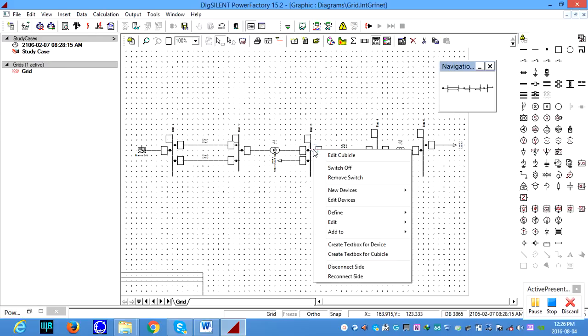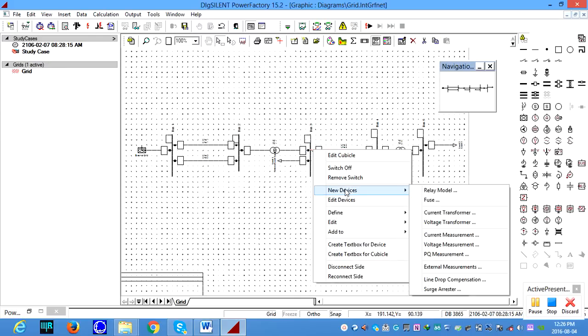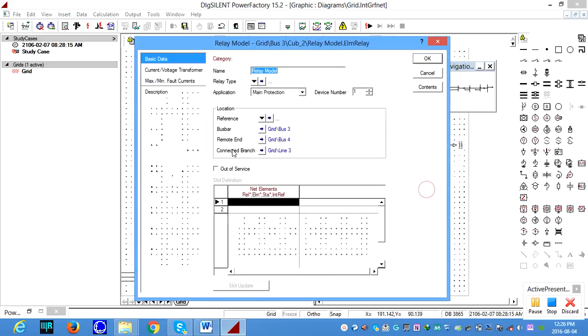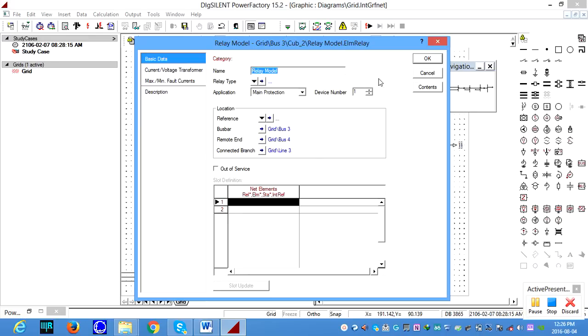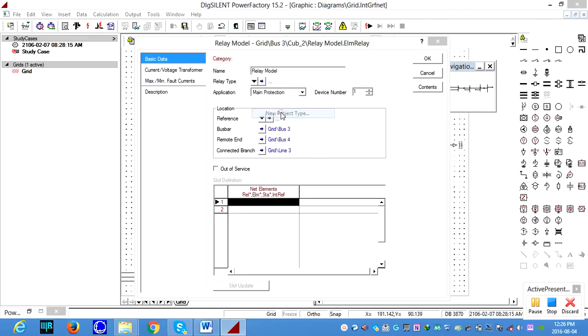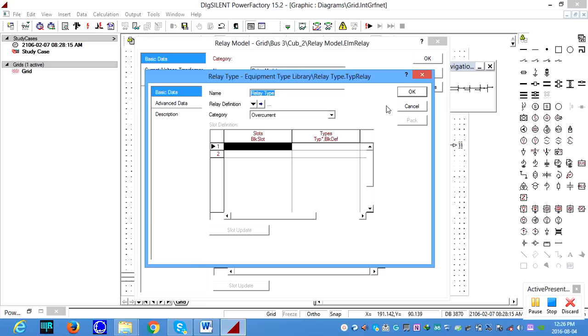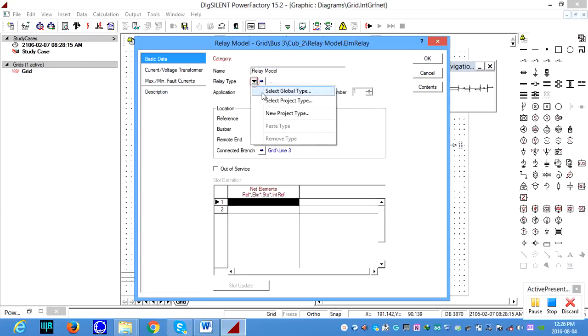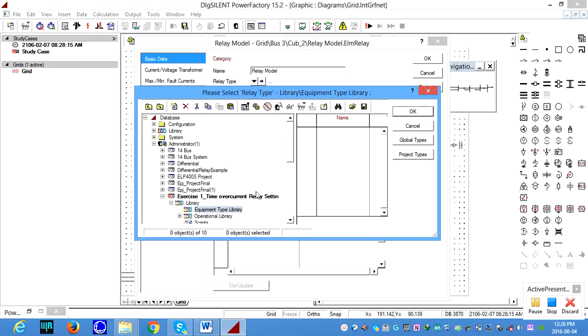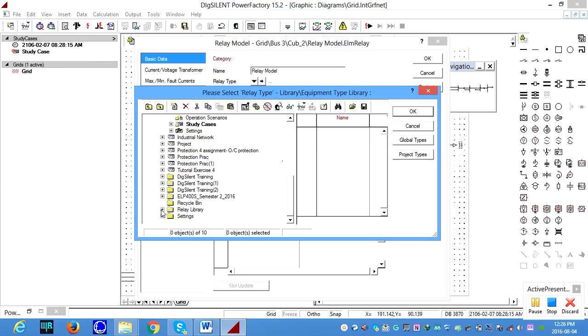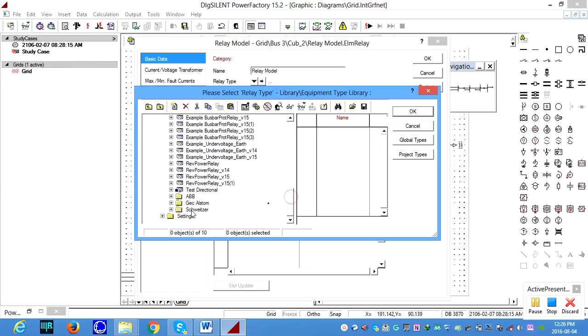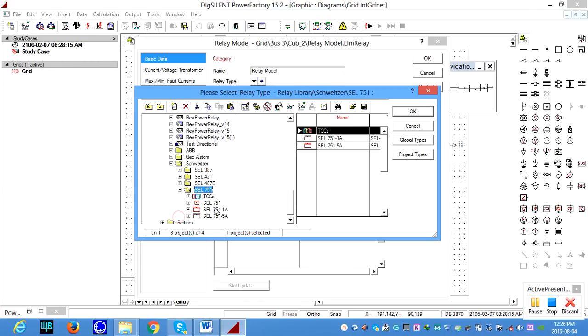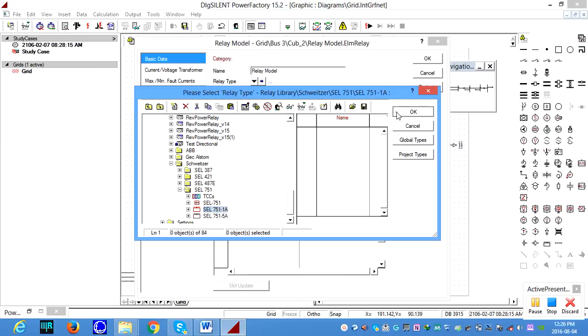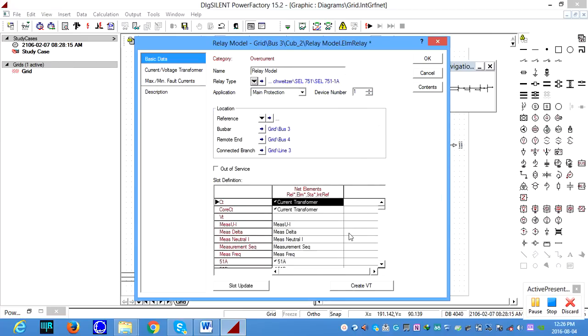So again, go here, bus 3, right click, new devices, select relay model, and then from here you can go and select the new project. Okay, sorry, you can select the project type, and then we need to go to the relay model, and then we go for SEL 751-1A relay. Okay, so now the relay settings 751 was imported, and also the current transformer.